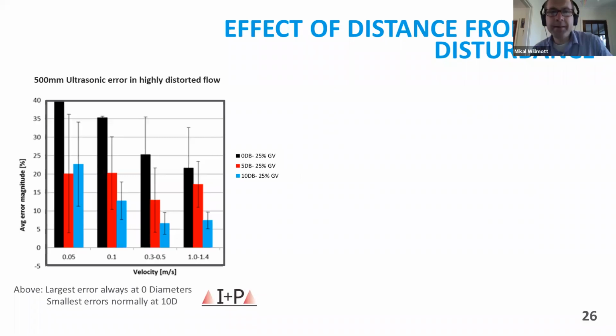Okay, so we then did some testing looking at ultrasonic meters, and I+P Services did this testing again at the NEL, at their 500 mil rig. And we tested quite a few ultrasonic meters. What you've got in this graph is average errors from a number of ultrasonic meters. The black bars are when we put the meter at 0 diameters, so right behind the disturbance. The red bars are 5 diameters downstream, and the blue bars are 10 diameters downstream. And again, we've done it in different velocity brackets there.